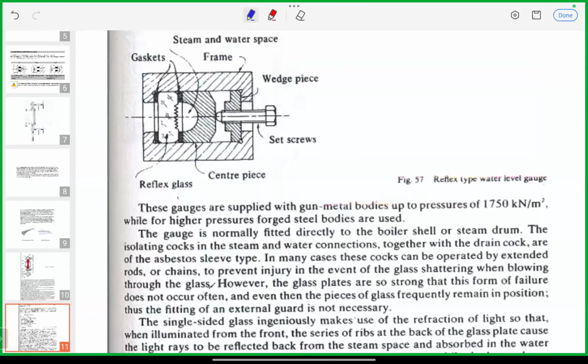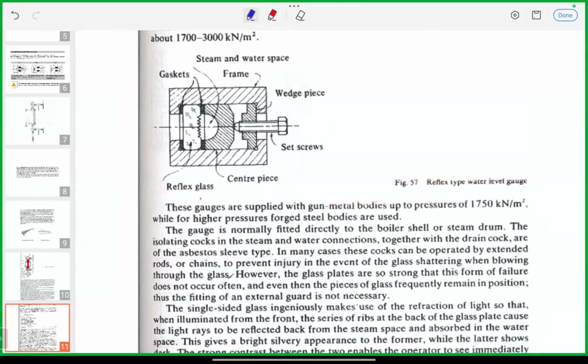Another type is the reflex type of gauge glass. It is used for most of the modern boilers. In this one you are going to have the reflex type of glass, generally applicable for your medium pressure boiler, and this works on the refraction of the light.